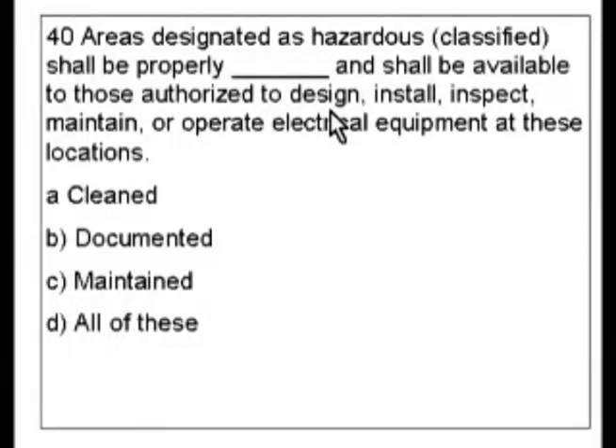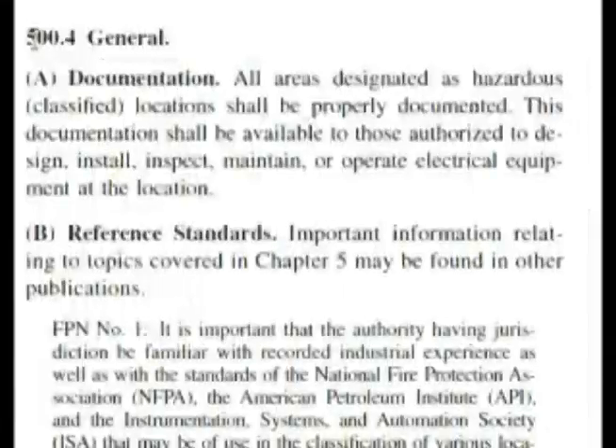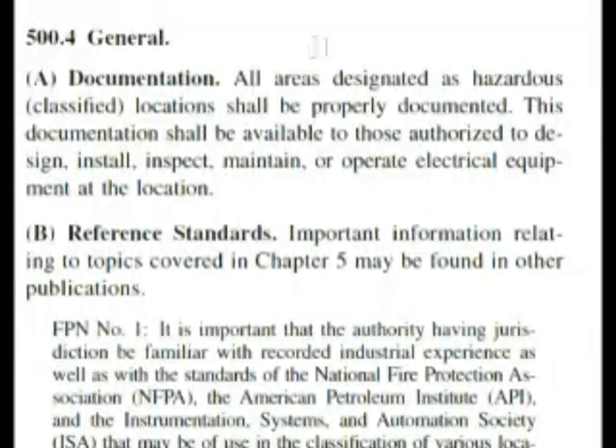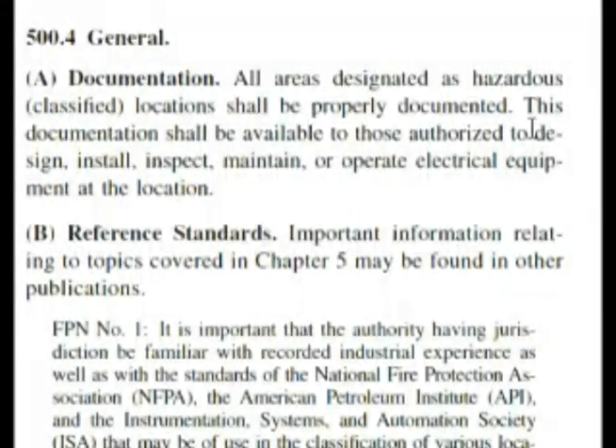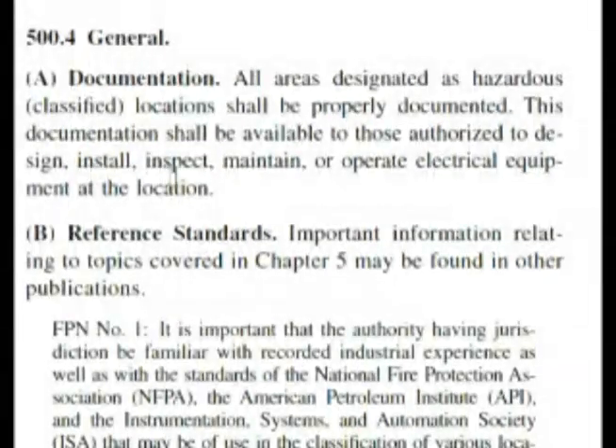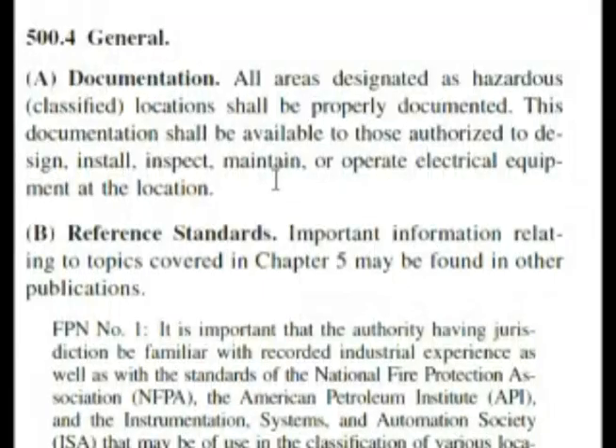Let's go back to the question again. It says areas designated as hazardous shall be properly blank. Looking in your index, hazardous takes several pages, so we're looking for a general type question right at the beginning — and that was 500.4 general. So let's go there now. Here we are at 500.4, and the very first thing says documentation. That was one of our potential answers. It says: all areas designated as hazardous or classified locations shall be properly documented. This documentation shall be available to those authorized to design, install, inspect, maintain, or operate electrical equipment at the location. That's word for word, pretty much, what our question was asking.